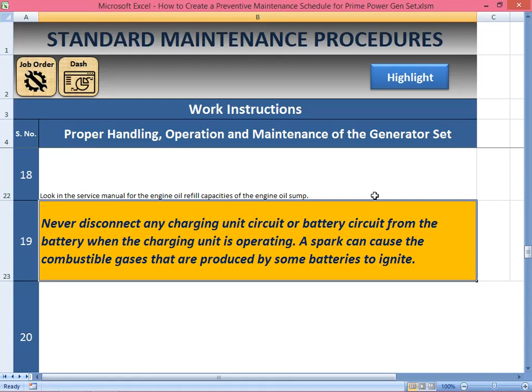To help prevent sparks from igniting combustible gases produced by some batteries, the negative cable should be connected last, from the external power source to the negative terminal of the starting motor. If the starting motor has no negative terminal, connect the cable to the engine block, so the frame of the generator set can also be used as ground.